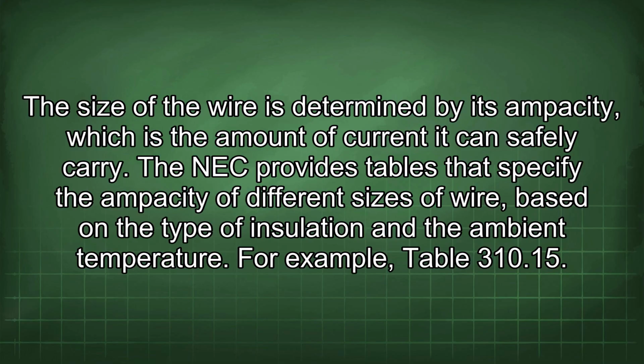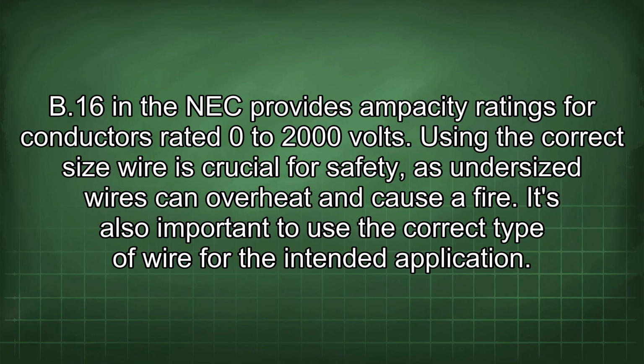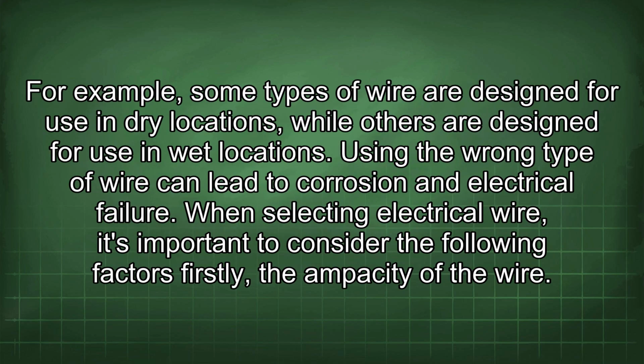For example, Table 310.15(B)(16) in the NEC provides ampacity ratings for conductors rated 0 to 2000 volts. Using the correct size wire is crucial for safety, as undersized wires can overheat and cause a fire. It's also important to use the correct type of wire for the intended application. For example, some types of wire are designed for use in dry locations, while others are designed for use in wet locations. Using the wrong type of wire can lead to corrosion and electrical failure.